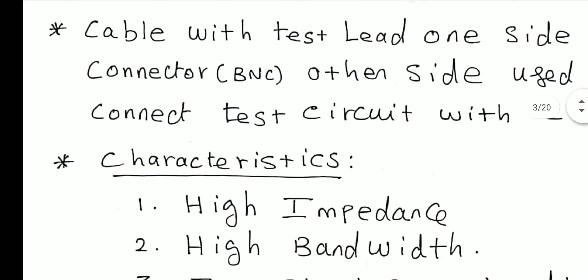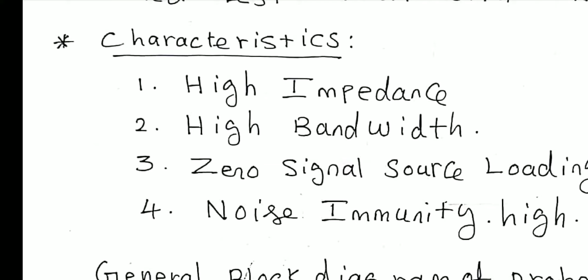See, any CRO probe, the good CRO probe should have this kind of characteristics. The major characteristics of a CRO probe is it should have a very high impedance and it should have high bandwidth. High bandwidth means that the probe should allow a wide range of frequencies, so that in a test circuit, from low frequency to any very high frequency signal, we can connect from the test circuit with CRO, right? For that, the cable should allow a wide range of frequencies. That is the meaning of high bandwidth.